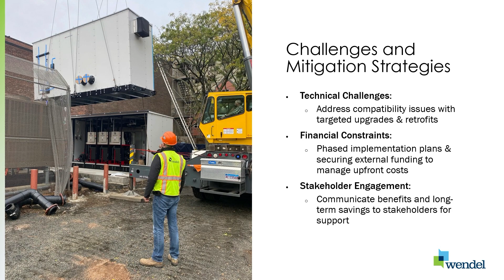It involved pretty much the building itself. Let me show you the initial setup. It was connected to a district steam system and district cooling system, and what they wanted to do was electrify the whole building, get it off of the steam plant. The challenges were reusing the coils, the hot water coils, and getting them to function with lower temperature hot water - we went with 140. And then getting rid of some of the steam uses in the building, like the preheat coils, the humidification for the labs, and other process uses such as glassware washers, autoclaves, and the like.